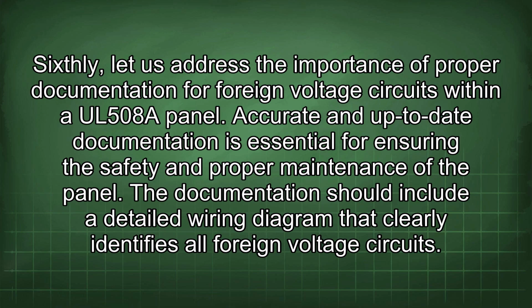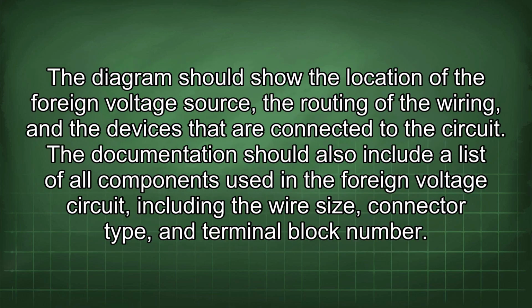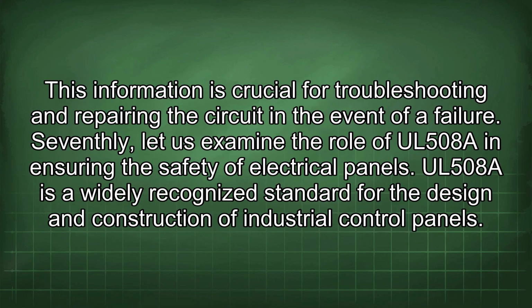Sixthly, let us address the importance of proper documentation for foreign voltage circuits within a UL508A panel. Accurate and up-to-date documentation is essential for ensuring the safety and proper maintenance of the panel. The documentation should include a detailed wiring diagram that clearly identifies all foreign voltage circuits. The diagram should show the location of the foreign voltage source, the routing of the wiring, and the devices that are connected to the circuit. The documentation should also include a list of all components used in the foreign voltage circuit, including the wire size, connector type, and terminal block number. This information is crucial for troubleshooting and repairing the circuit in the event of a failure.